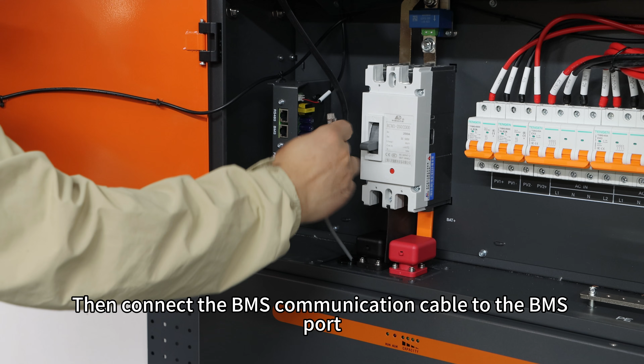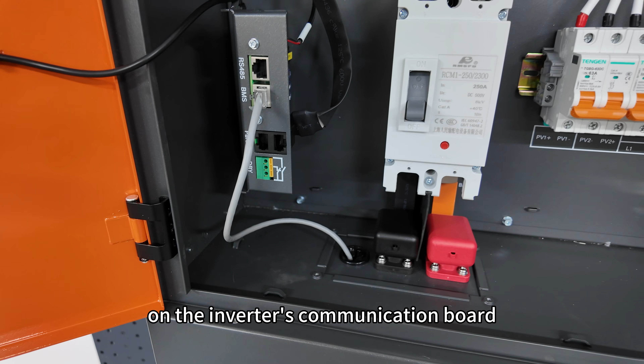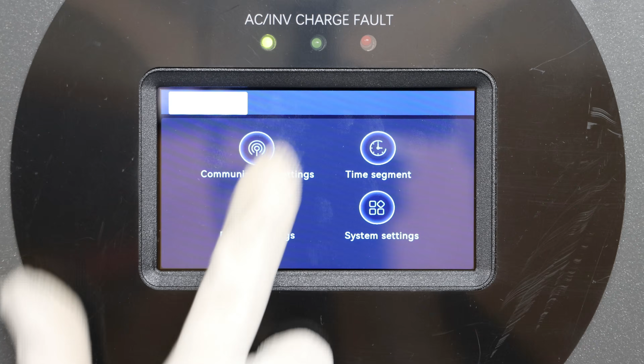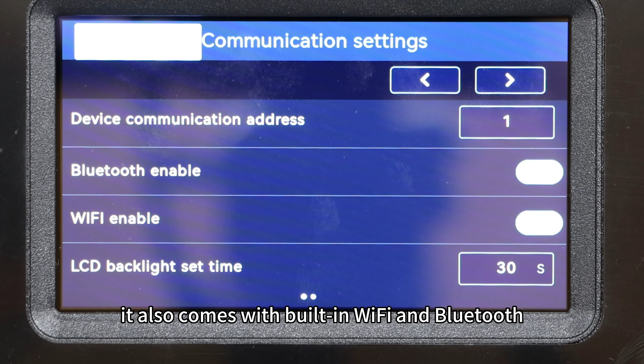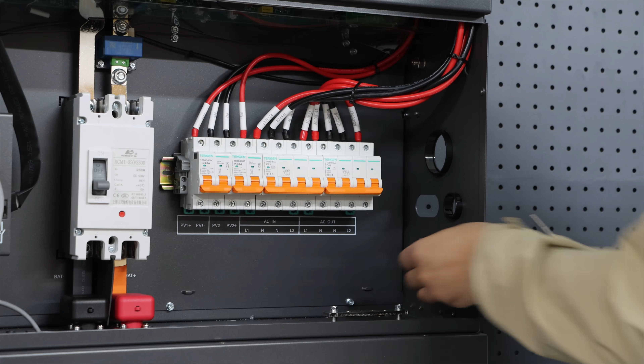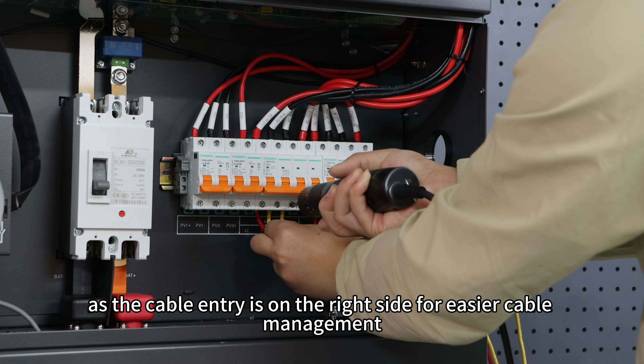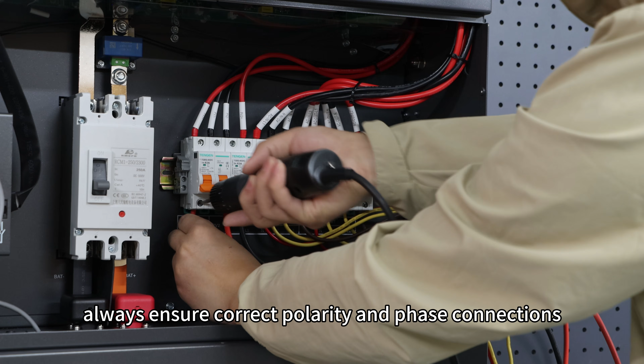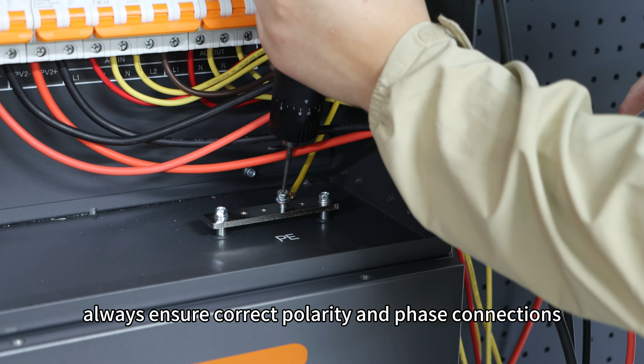Then connect the BMS communication cable to the BMS port on the inverter's communication board. Besides the BMS communication, it also comes with built-in Wi-Fi and Bluetooth, making remote monitoring and setup much easier. Next, connect the AC output, AC input, and the 2 PV inputs in order. We recommend wiring from left to right, as the cable entry is on the right side for easier cable management. During wiring, always ensure correct polarity and phase connections. Connect the grounding wire to the grounding bar.